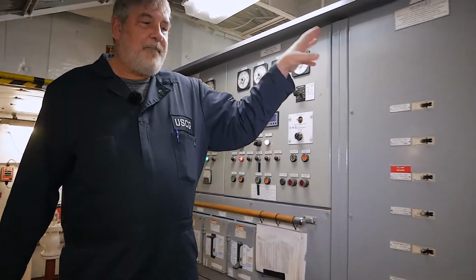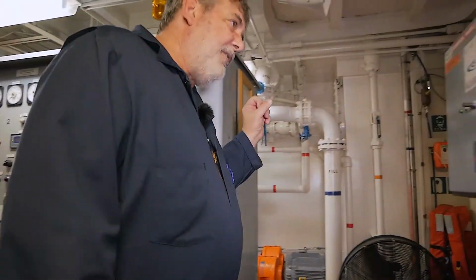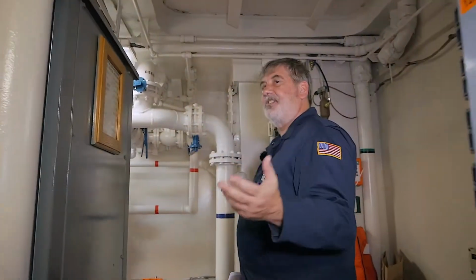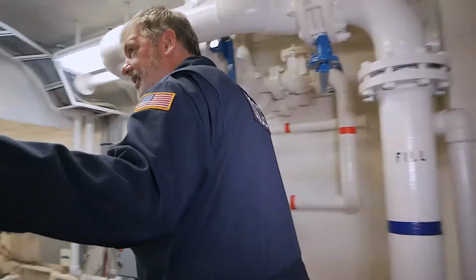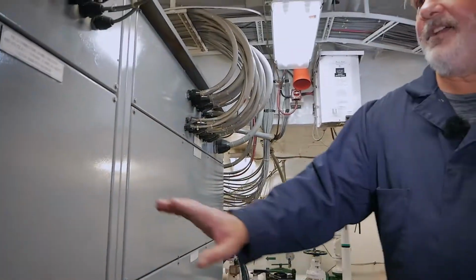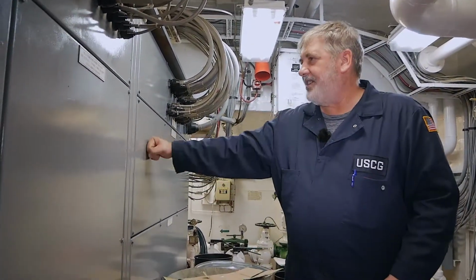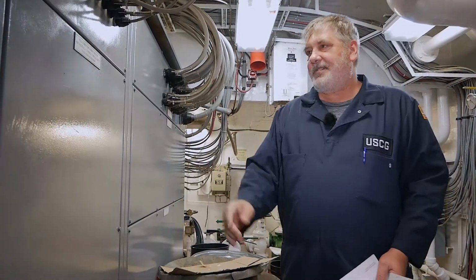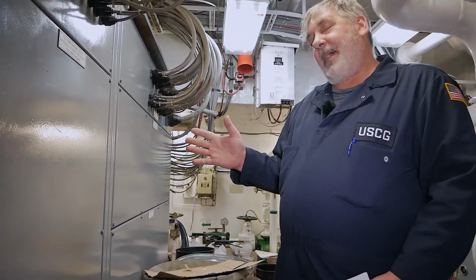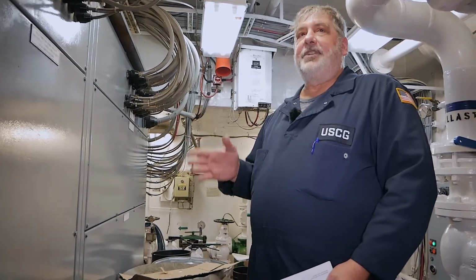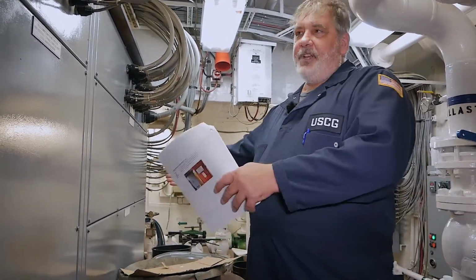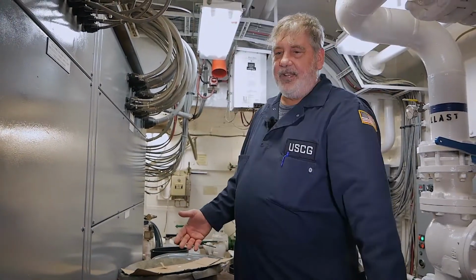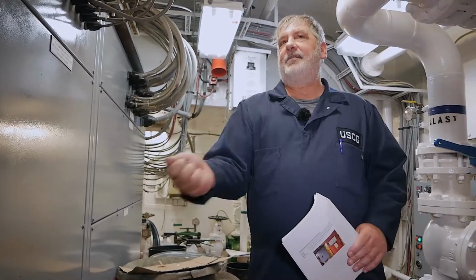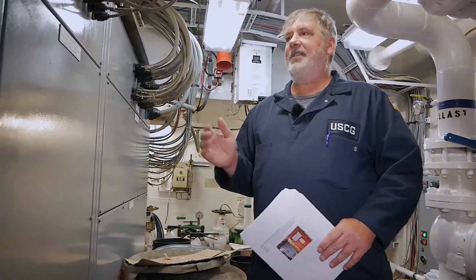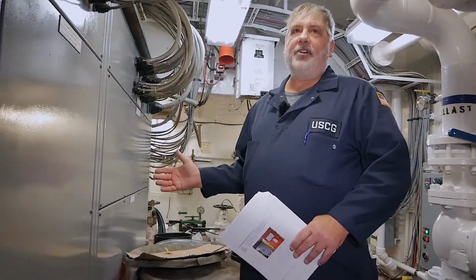Additionally, the back of the switchboard is required to be just as safe as the front. And as you can see, the back of the switchboard is enclosed as well. There are no openings. Open back switchboards are allowed, but there are special rules. If you encounter one, then it has to be sealed off with a gate, and it must be locked and controlled by the chief engineer probably.